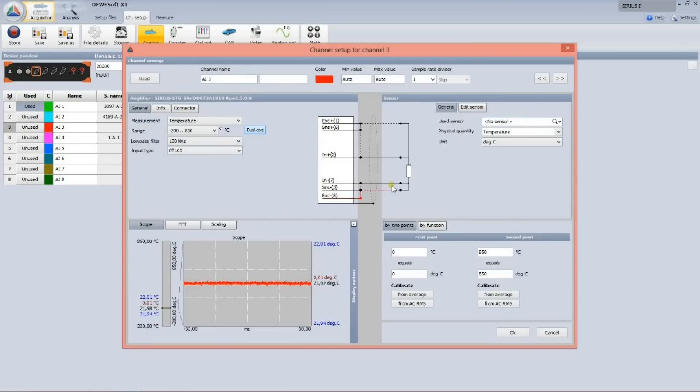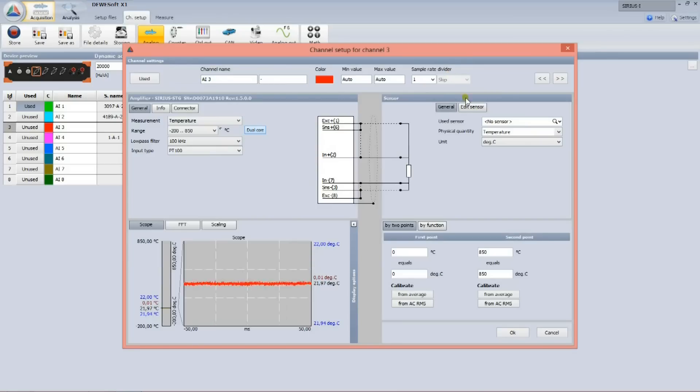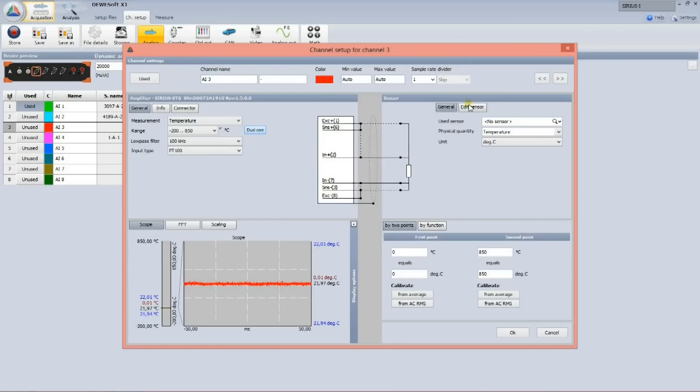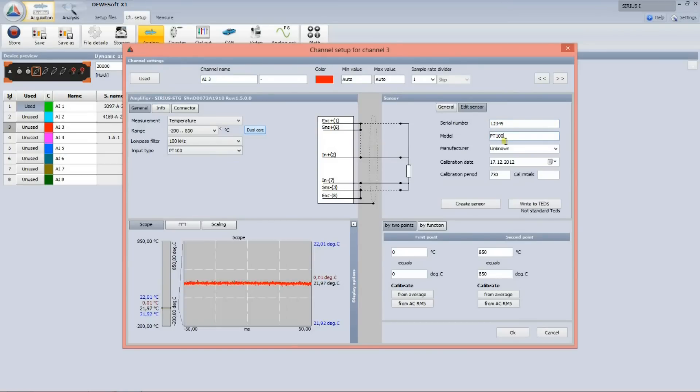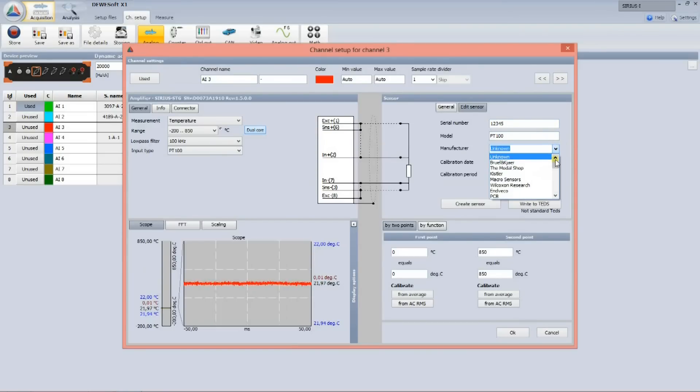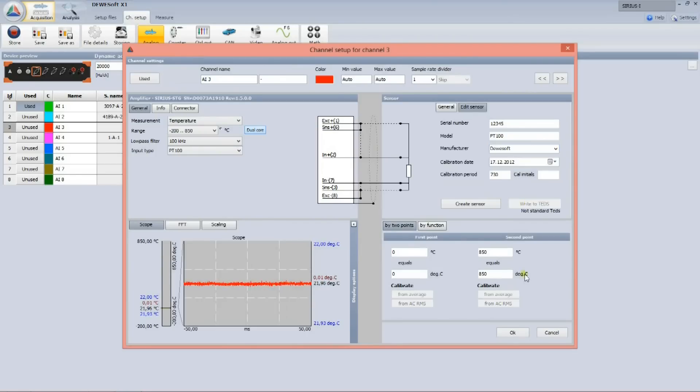In the middle of the screen, I see how the sensor must be connected, and I can define the sensor scaling. Then I can simply enter the sensor serial number, sensor type, and manufacturer, and by writing this info to the TEDS, a smart sensor is created. When I leave the channel setup, sensor is already shown.